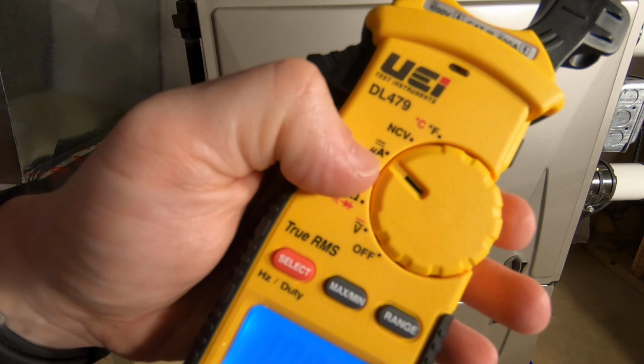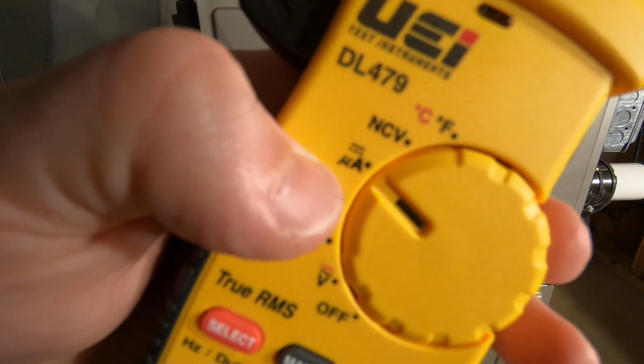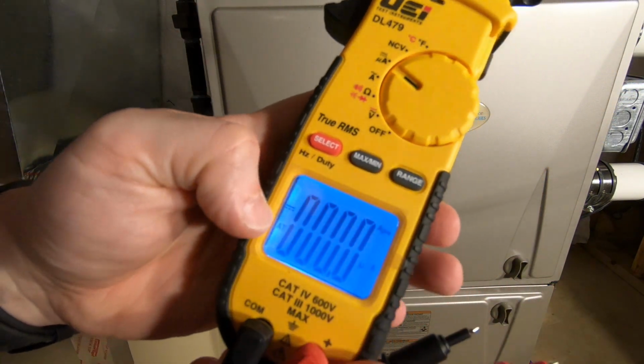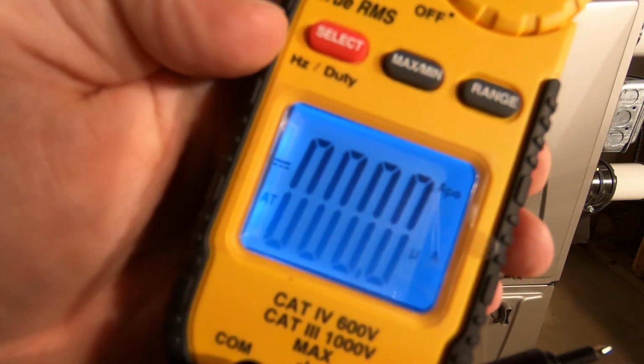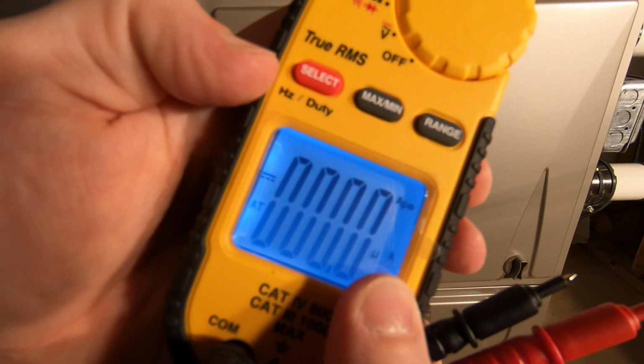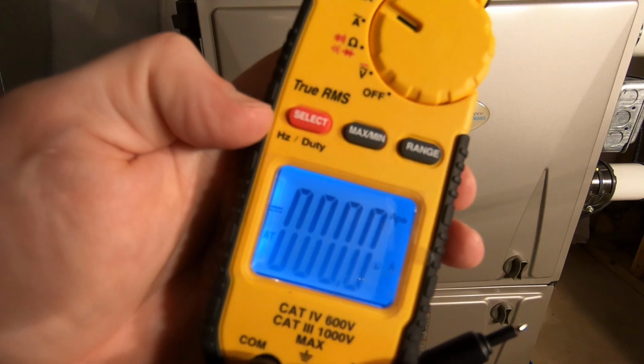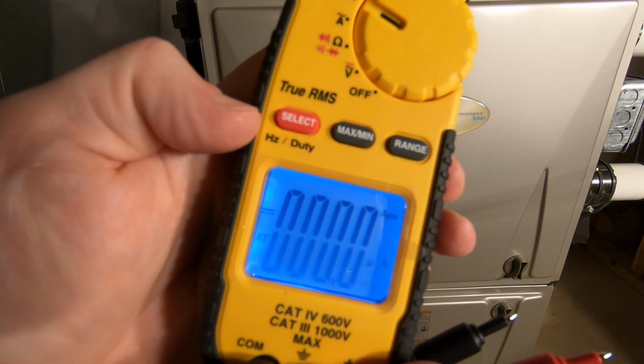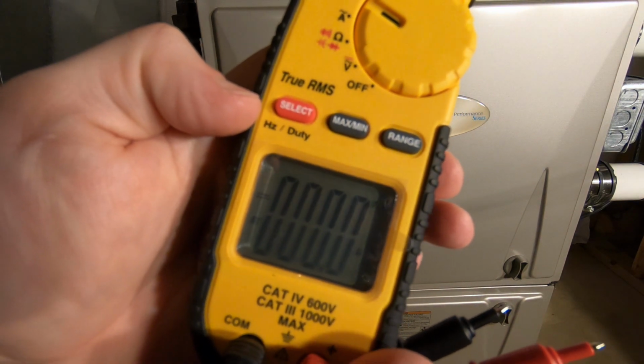Here we can see the next setting I just switched it to is DC microamps. Down here on the meter, you can see now it says UA, so we can read microamps on a furnace. Microamps would be what we use for flame sensor.